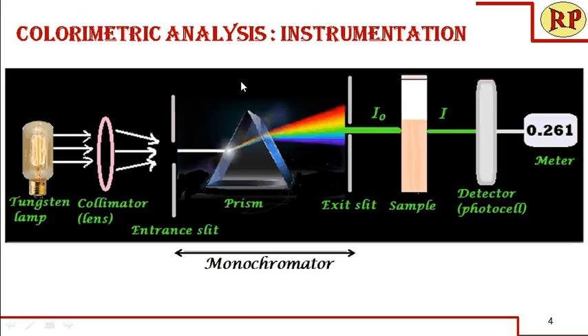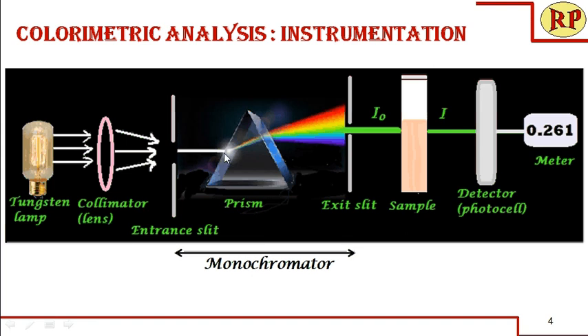Let us look into the outline of the instrumentation of colorimetric analysis. This is a tungsten lamp, which is a source of visible light supplying light between 400 to 750 nm. We use a collimator — a lens — which narrows down the beam and aligns the light. The aligned light is then passed through an entrance slit, where a narrow beam of white light enters. This whole setup is called a monochromator.